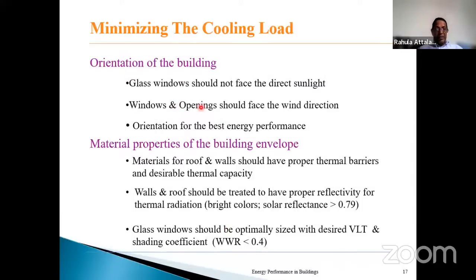So I have explained why the orientation is important. Then I have also indicated why material properties of the building are going to be important. Two other important things are the roof and the outside building wall colors. If dark colors are used, the absorption of the solar radiation will be very high. Therefore, in a tropical climate like ours, it is always better to have light colors so that the radiation falling onto the building walls and the roofs can be reflected back. Therefore, less heat exchange will take place from the outside to inside. The standards will say that solar reflectance, that is, 79% of the radiation should be reflected. The materials used should be of this order.